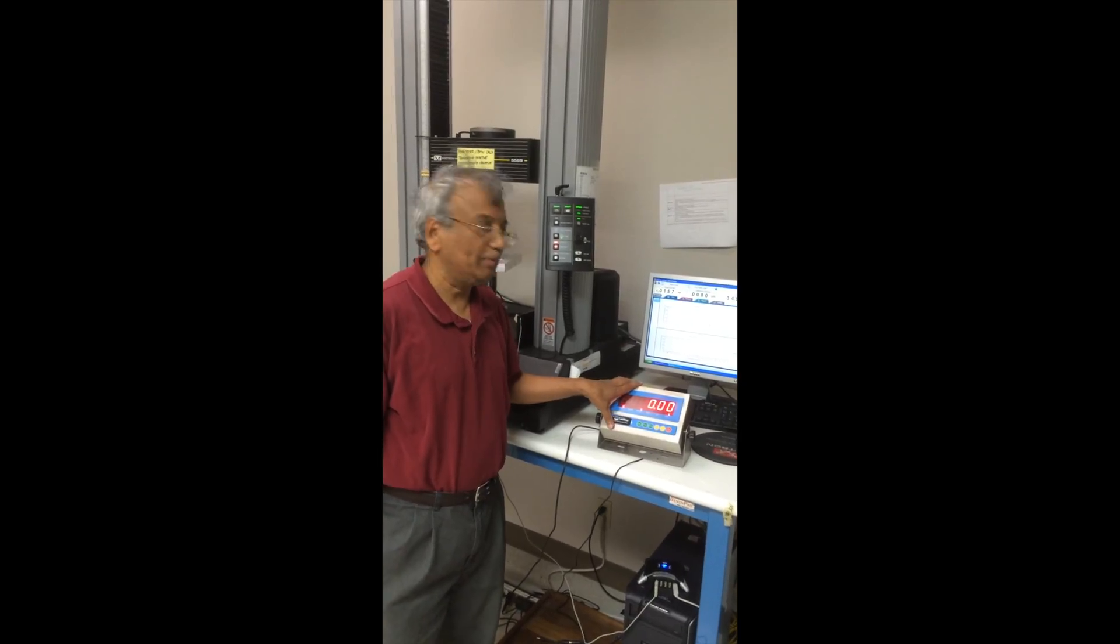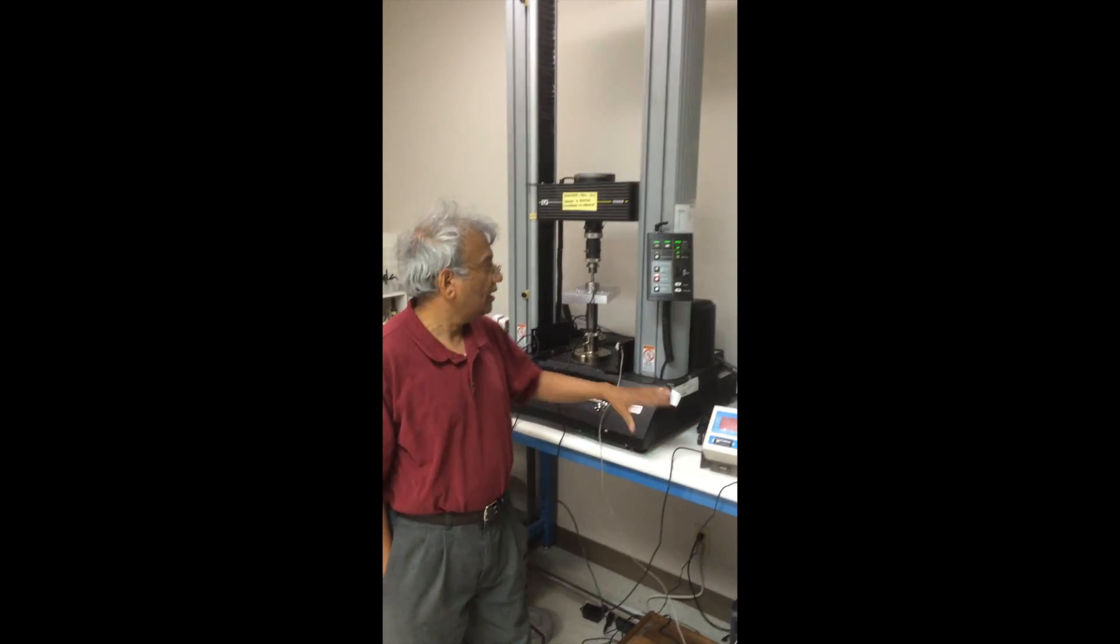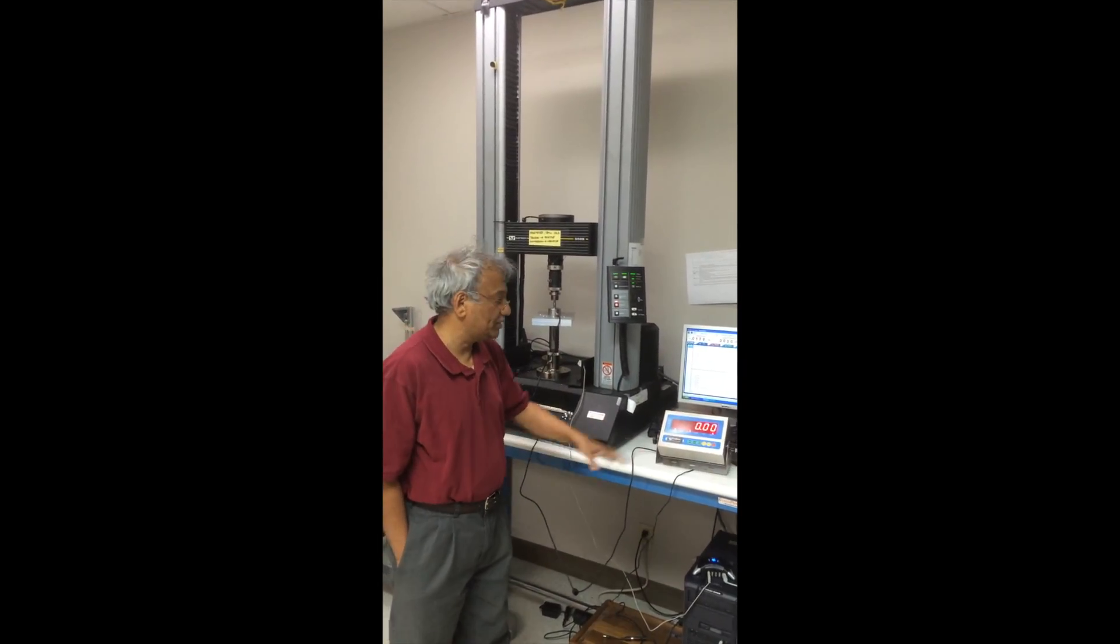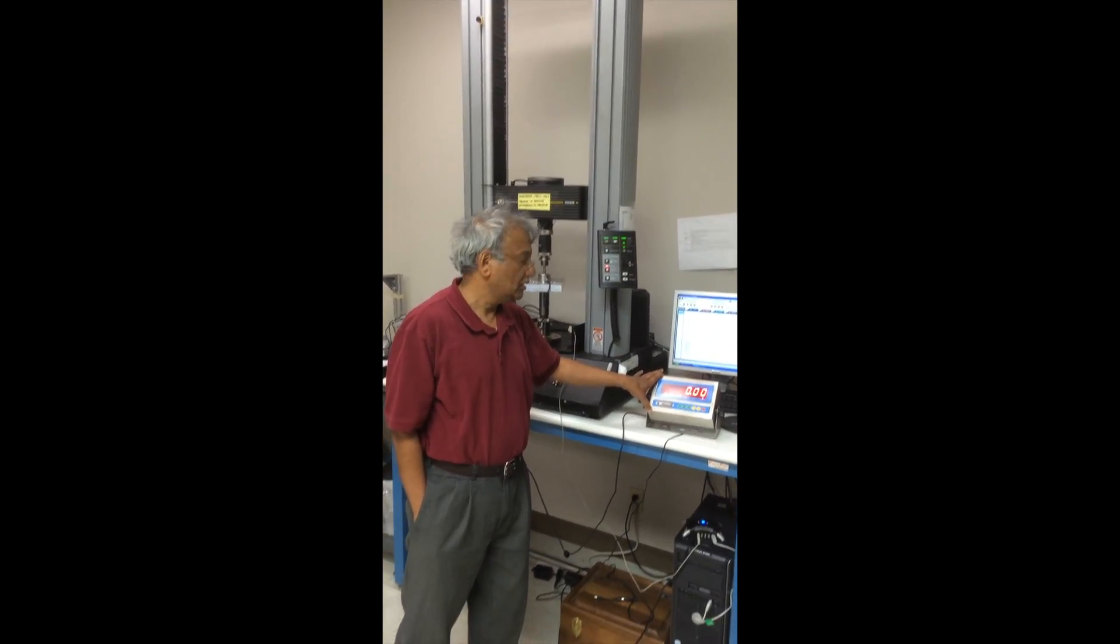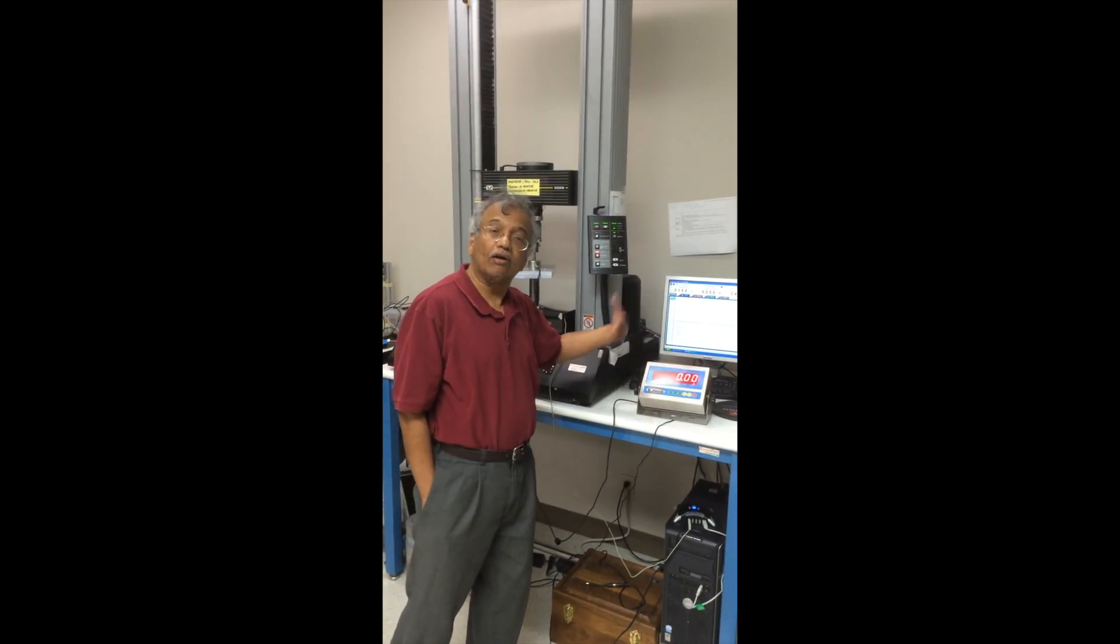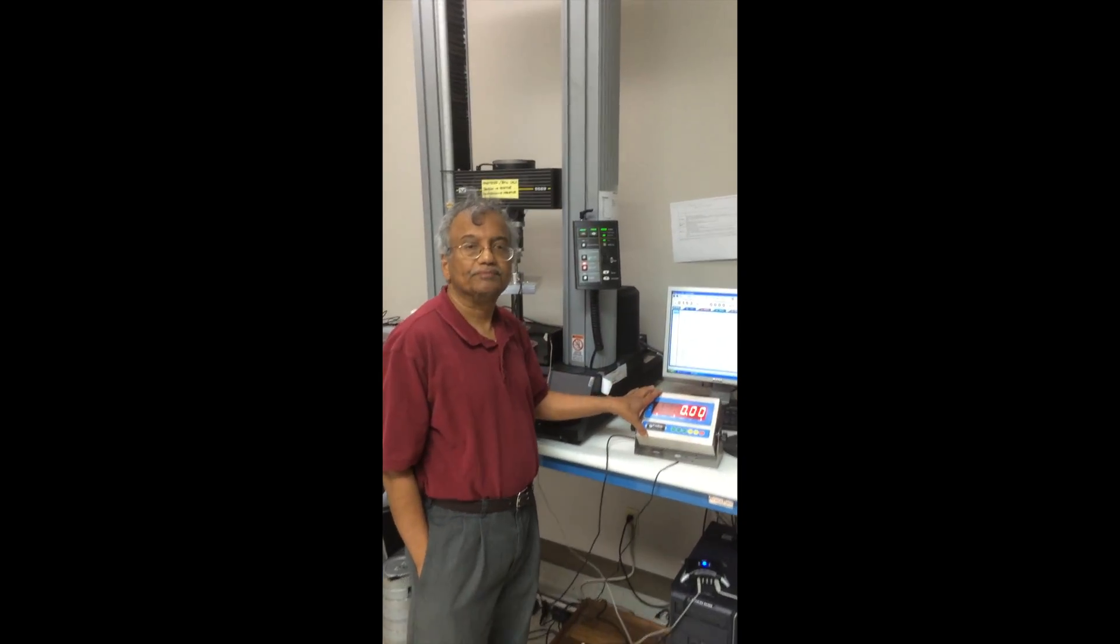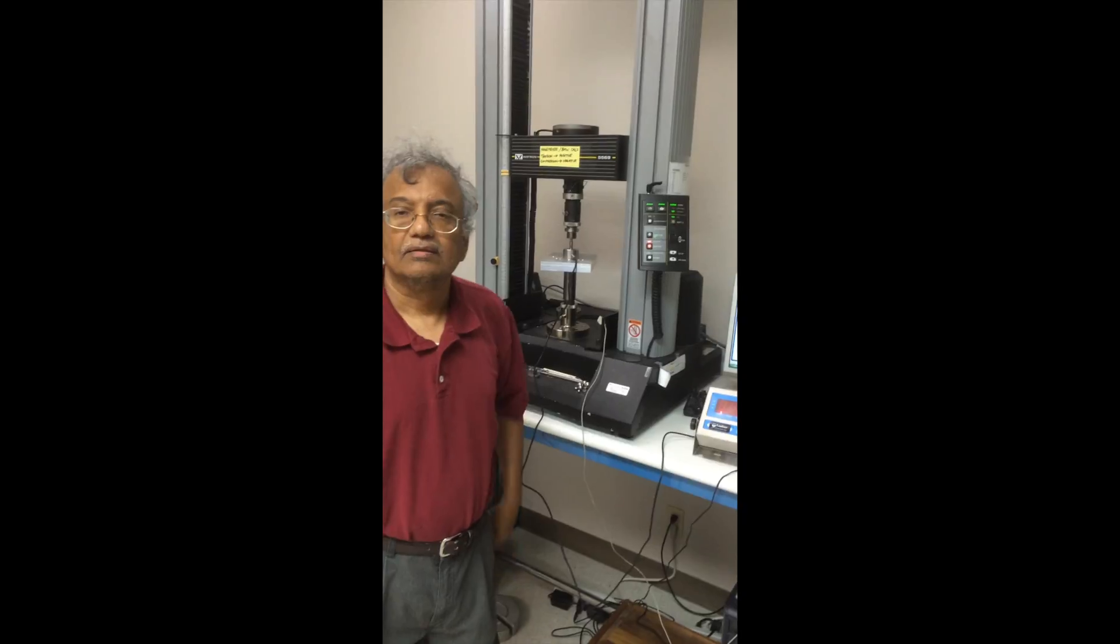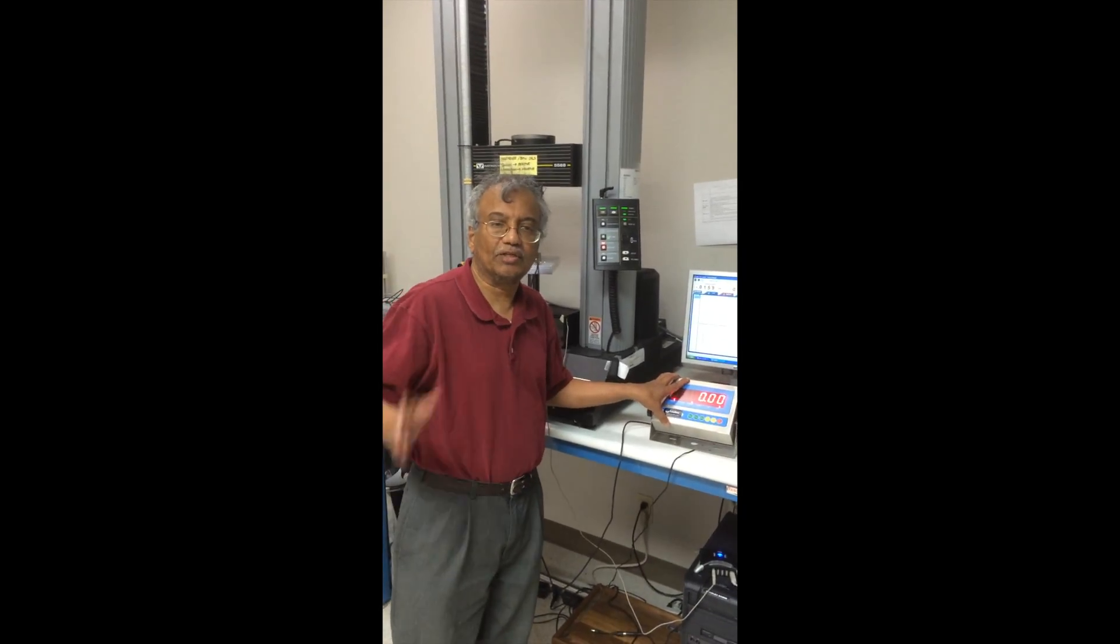That's how you calibrate a load cell with RD-1000. And you can use any load cell. And if you have dead weight, you can use dead weight. Apply it as long as you can apply a steady load. And you can calibrate in tension or compression. But you can't calibrate in both. Thank you. Thank you from Loadstar Sensors. This is Saundar.